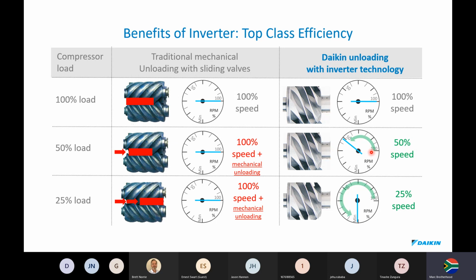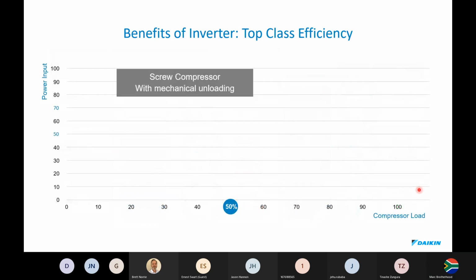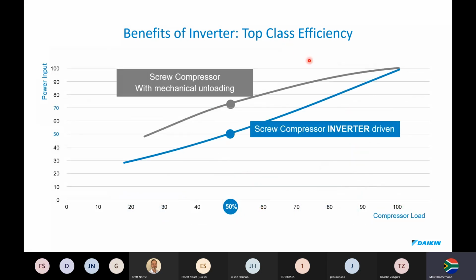And here you can see at 50% speed, we drop the RPM right down, and we have around 25% speed. We have to spin at a minimum rate so we don't have mechanical stall. And our inverter still generates a bit of back EMF on the electrical motor, so we still have to maintain a minimum anti-stall speed within our system. So what are the benefits of the inverter? Well, we have the best efficiency in the market.